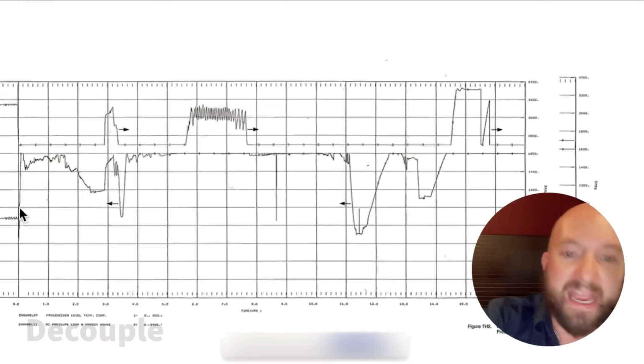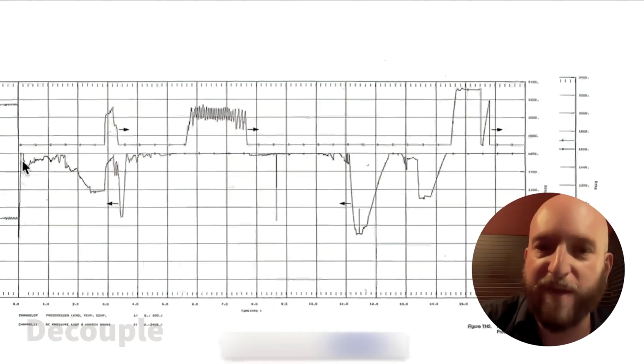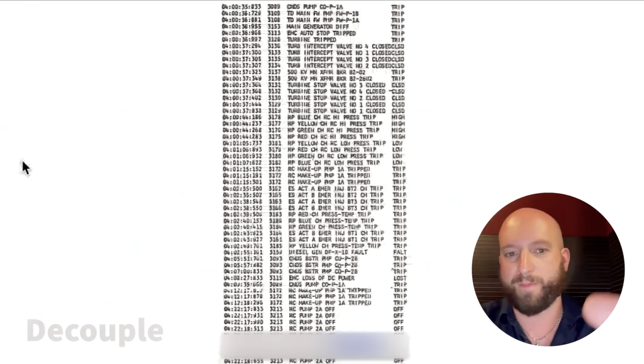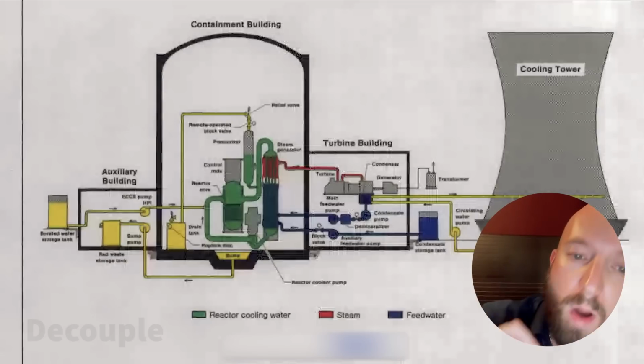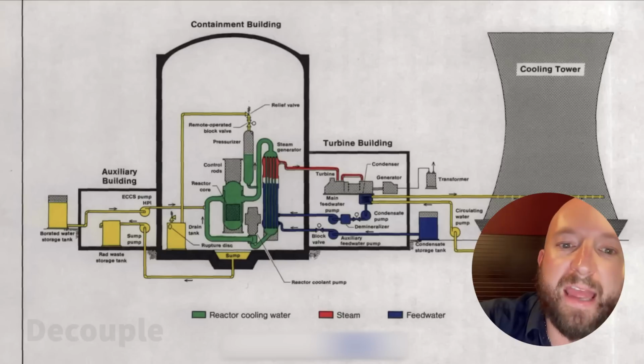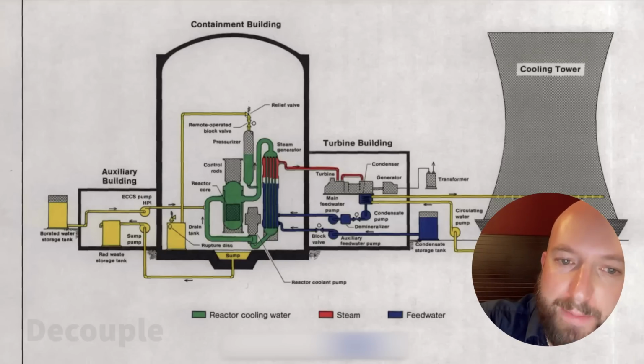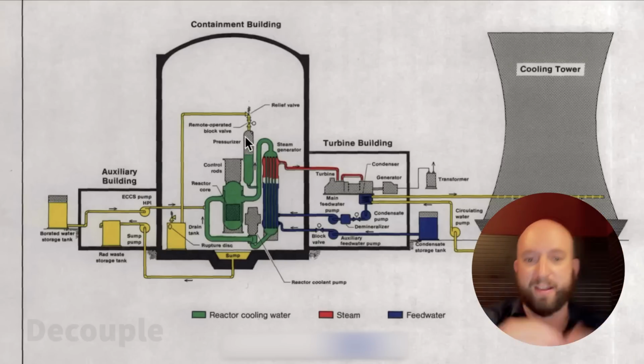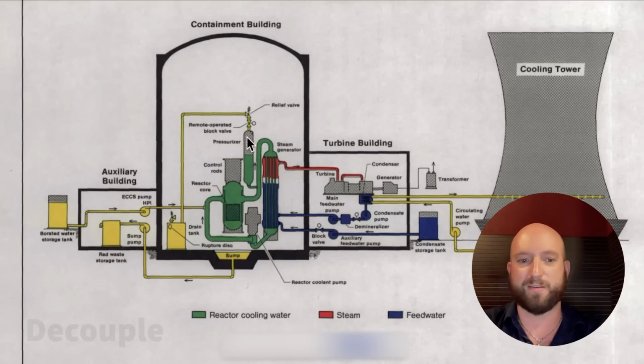So like tens of inches higher, like feet higher than is normally expected. And remember how I said one of the things that they are trained to do is never let go of that steam bubble on the top of the pressurizer. That's called letting the system go solid.